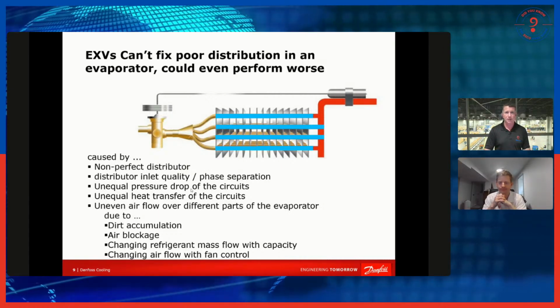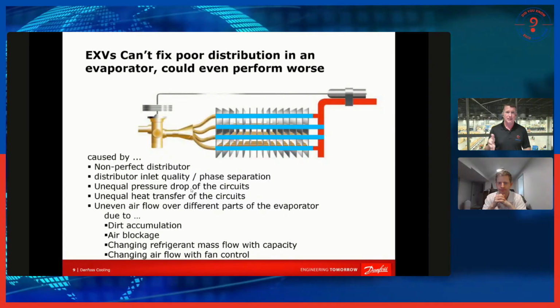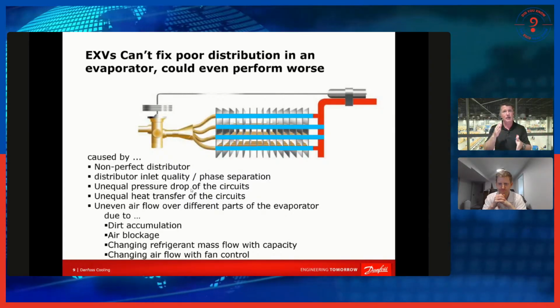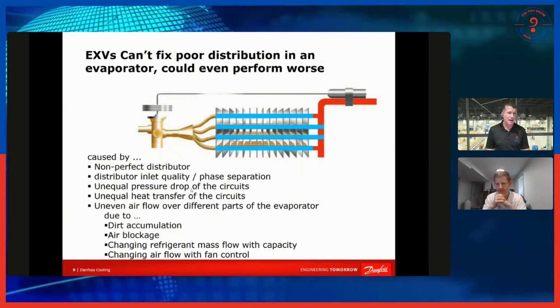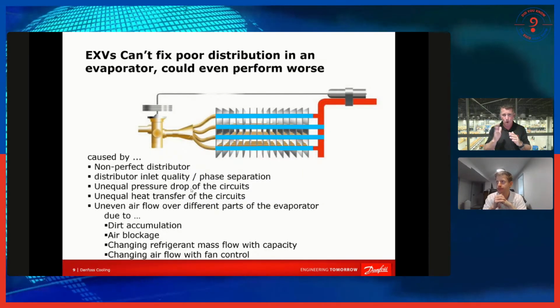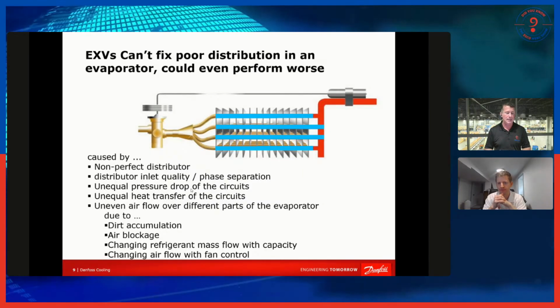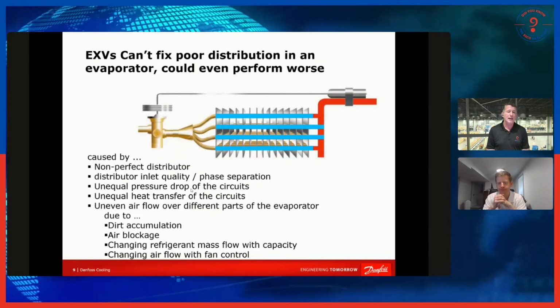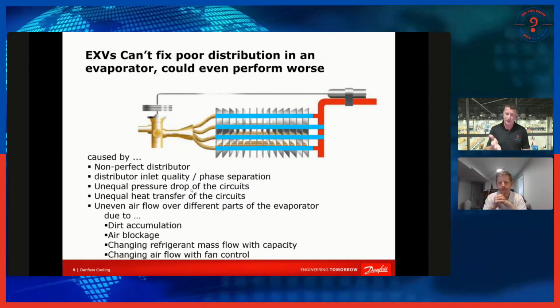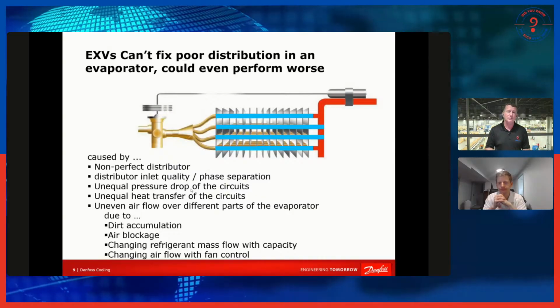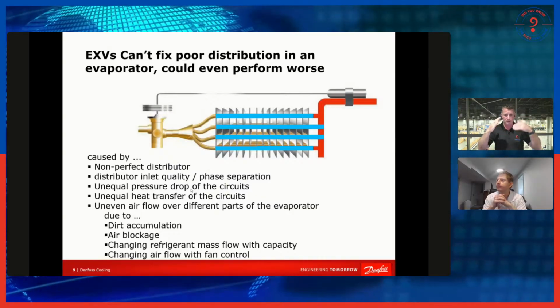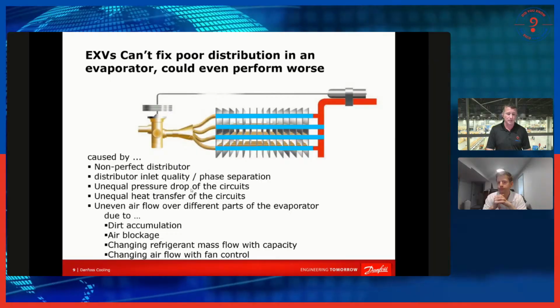Because during that cooling, we lose a portion of our airflow, and now all of a sudden we have unequal airflow through the evaporator, especially when we start looking at multiple slab coils like N and M coils. It really can have an effect on that. And so understanding, like you said, how the superheat is flowing through the coil is critical, because it's looking at more of an average, really.